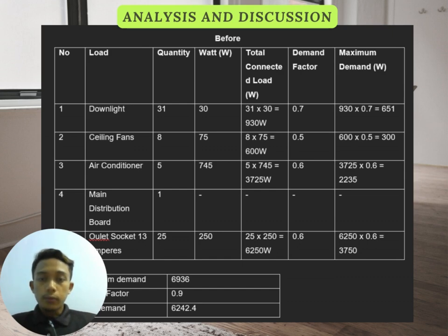To know the total connected load, we multiply the quantity of the equipment by the power use of the equipment, so we get the total connected load for each equipment. Then we find the maximum demand by multiplying the total connected load with their demand factor, so we get the total demand.